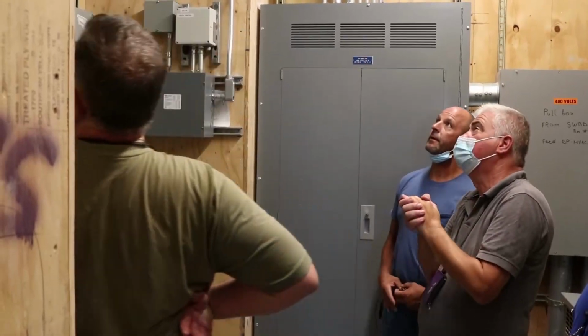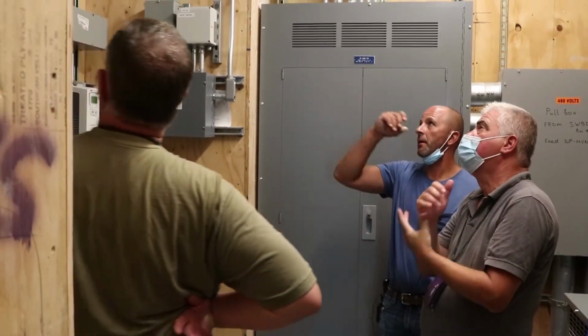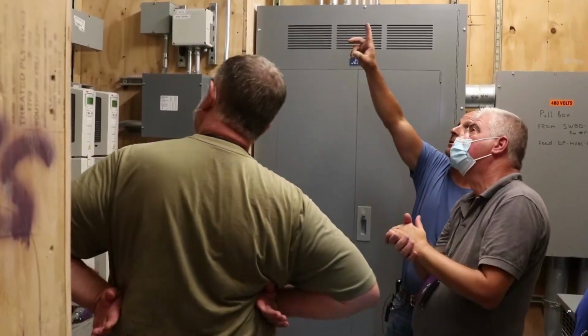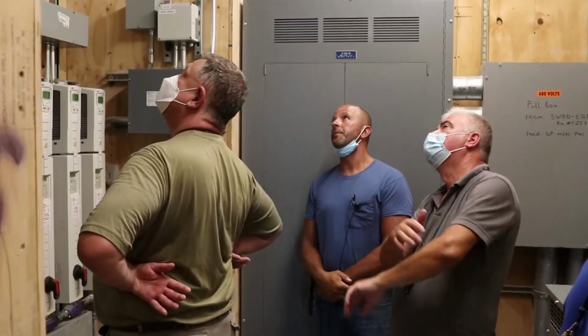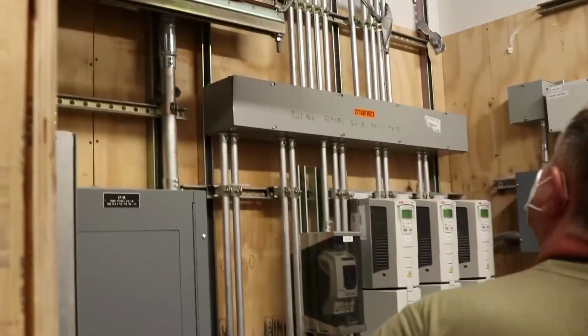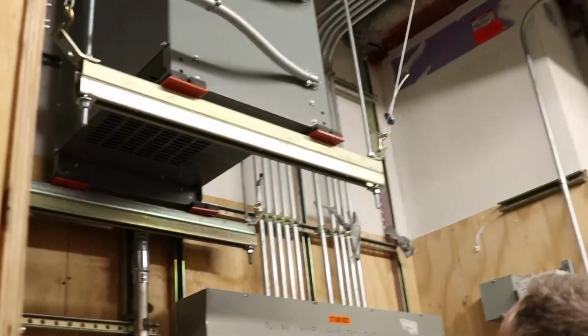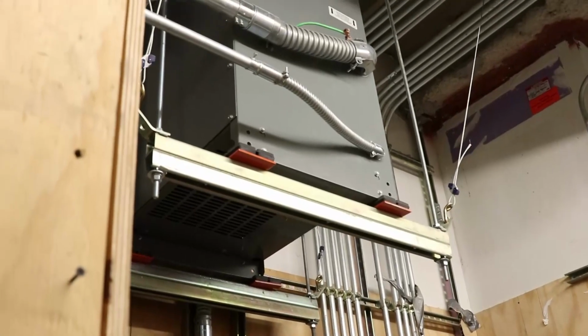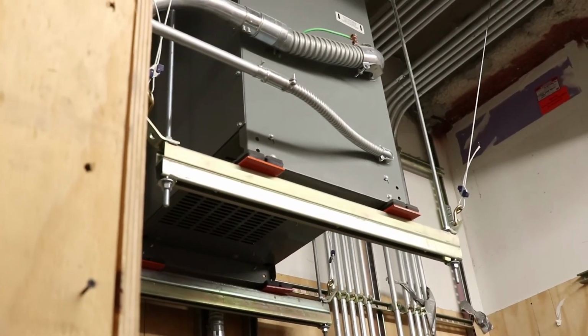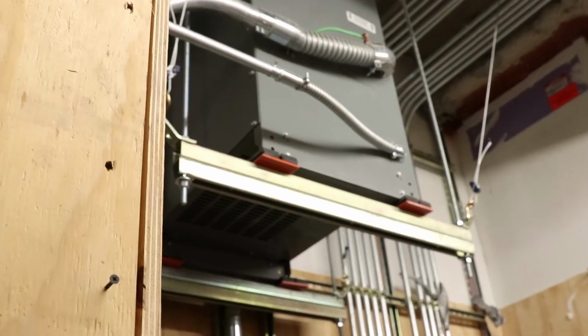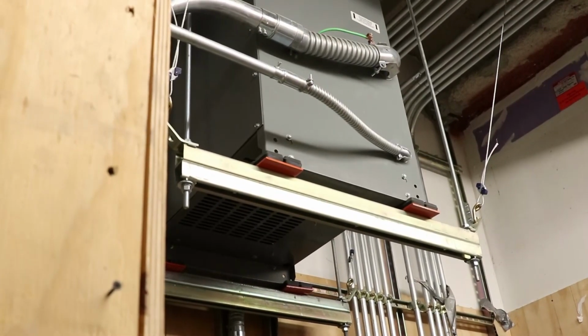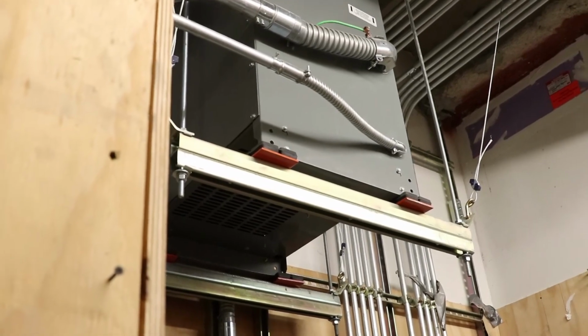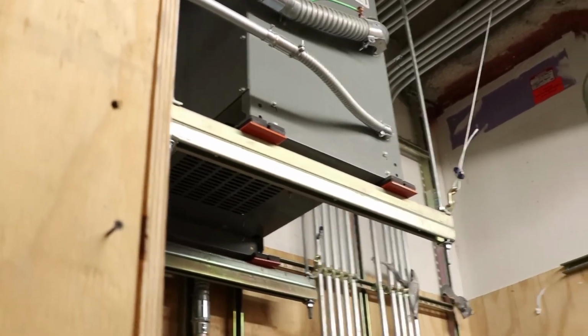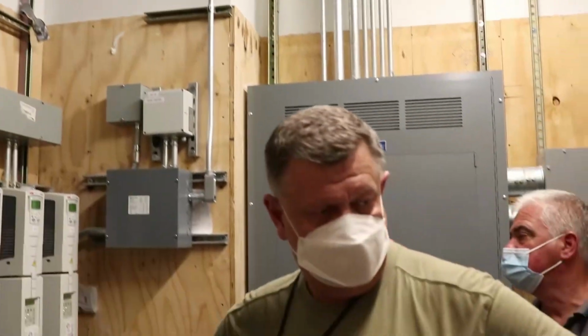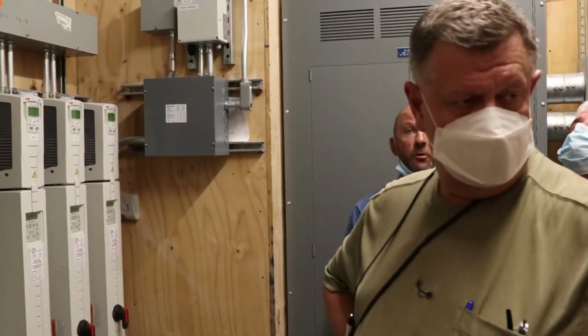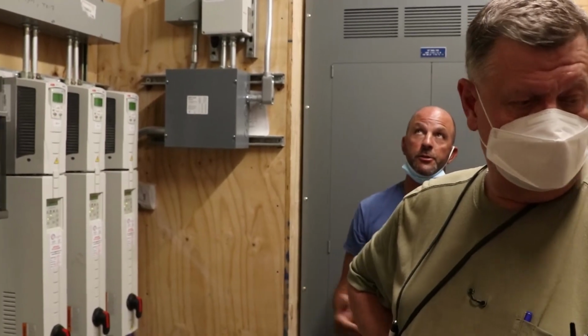Yeah, that's a good indication of what the seismic looks like, those cables. That's exactly how it is. Ours are a little different - we use gripples where you run them through and they hit 2 spots and grab. It's just a different brand, but that's a seismic application right there with the cables. There's nothing you do for it - it's just if it's over a certain weight or height, they make you put them on. It's not everywhere - you won't see it on small pieces of duct like this, only when it gets above like 30 inches or so.